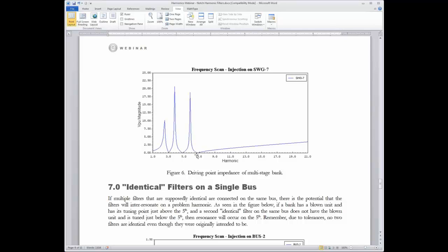This also, basically what happens is, you can see that this doesn't necessarily go all the way down to zero impedance here. The smaller you break this up into pieces, making 3, 5, 7, 11, and 13, you could break this up a bunch if you wanted to, you'll find that you're not going to filter as effectively each one of those harmonics.